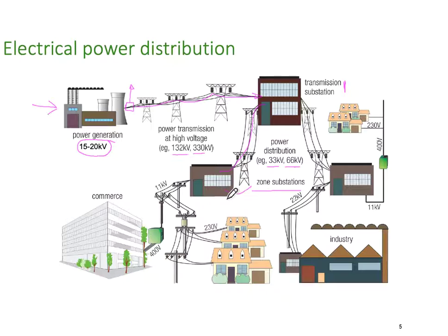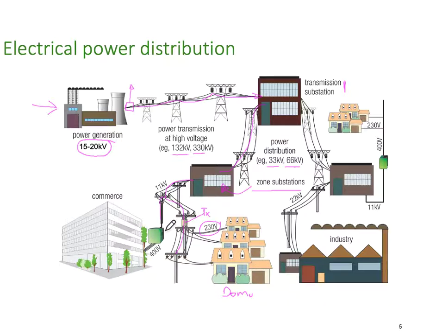At the zone substations, the voltage is again reduced through transformers and comes along the tops of poles. There's another transformer — I use the abbreviation TX for transformers — which breaks the voltage down to about 230 volt single phase to supply domestic houses. Also, coming down through another larger transformer, we supply 400 volts into a commercial building.